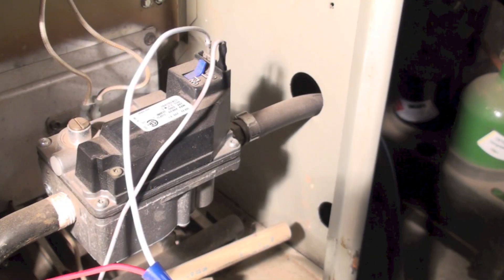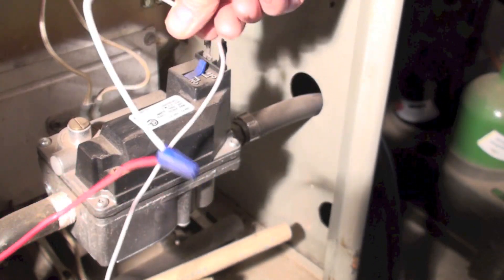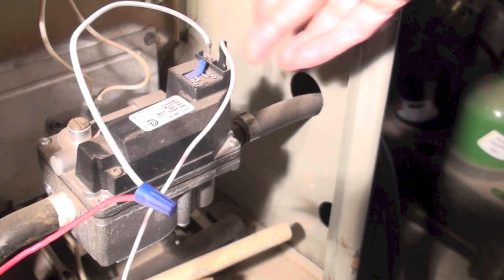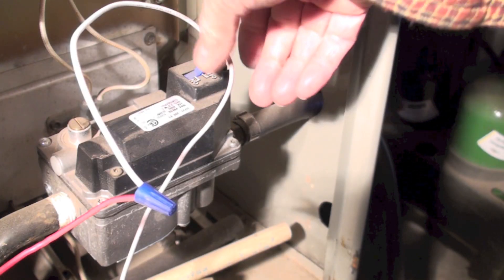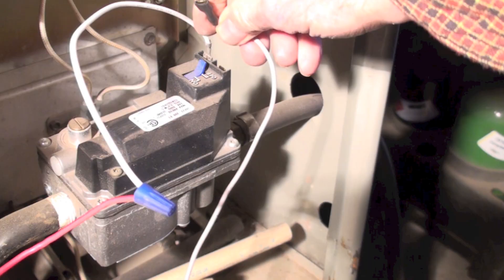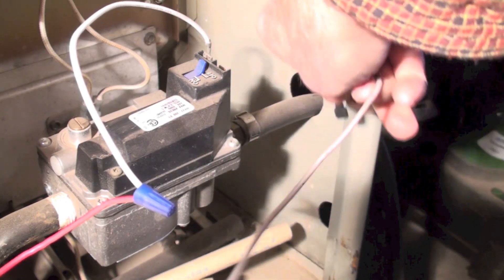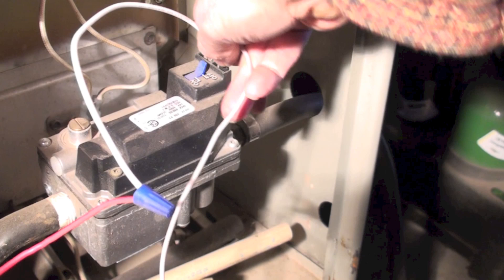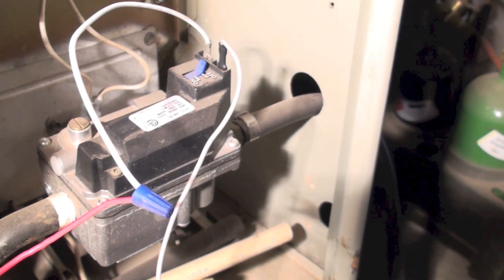This valve would be a pretty simple one — there's just two wires coming to it, no jumpers or anything. Some of these have jumpers. If you wanted to check this one, it has an insulated probe, so you can put your probe in there and put your other probe on the other one — that's how you test that one.